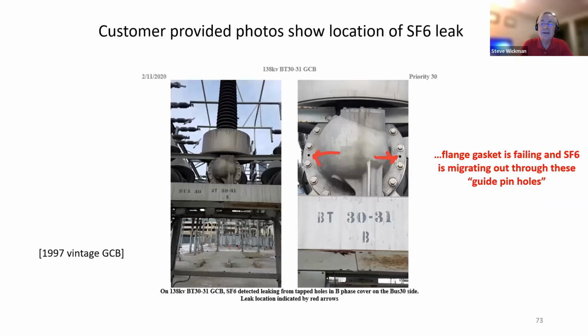In this case, the customer had offered up with their leak detection tools that this breaker was leaking through those guide pin holes. It's where they put a rod on there to guide the internals of that breaker to take it out for maintenance. SF6 was leaking through those holes. So a simple solution, well, just plug the holes.